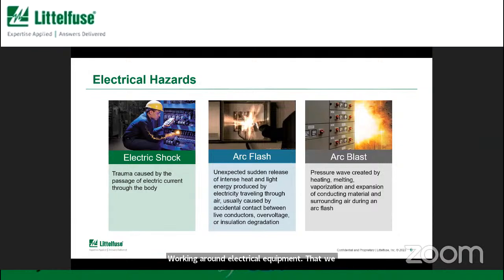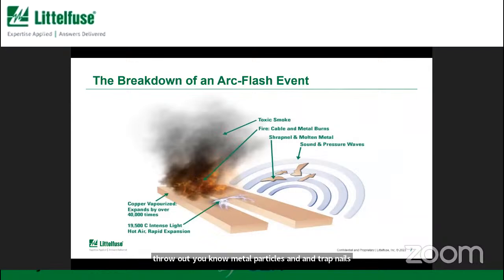Then we have arc flash. So that is a really intense release of energy that occurs when you have current flowing where it is not supposed to flow. So normally air is supposed to be a barrier, but when you have current going across that barrier and arcing, it does release a lot of energy. And then an arc blast: when an arc flash occurs, it does pressurize that piece of equipment, and it can create a blast that can throw out metal particles and shrapnel into the air. So we are looking at the arc flash event. So as I mentioned, if you have two copper bus bars separated with an air gap, that air is an insulator.